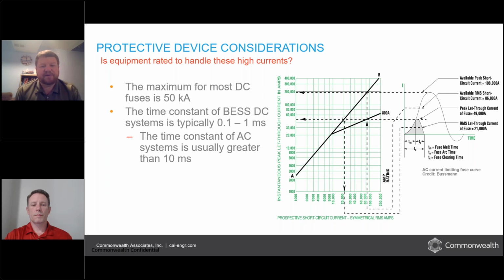This is a nice chart provided by Bussmann, and this allows you to compare. If I have an application with such a fault current and I apply this fuse, I can tell what the maximum fault current allowed through that fuse will be. And this makes the analysis of current limiting fuses quite straightforward and simple. So this is very nice when working with current limiting fuses in the AC world, and there are a lot of times where this makes a lot of sense.